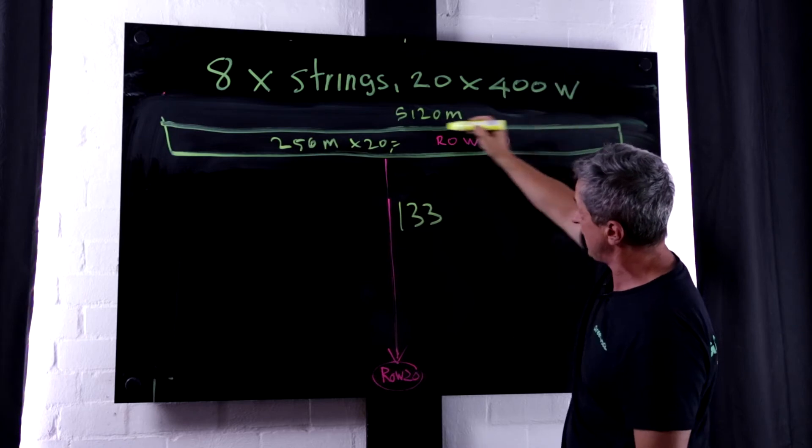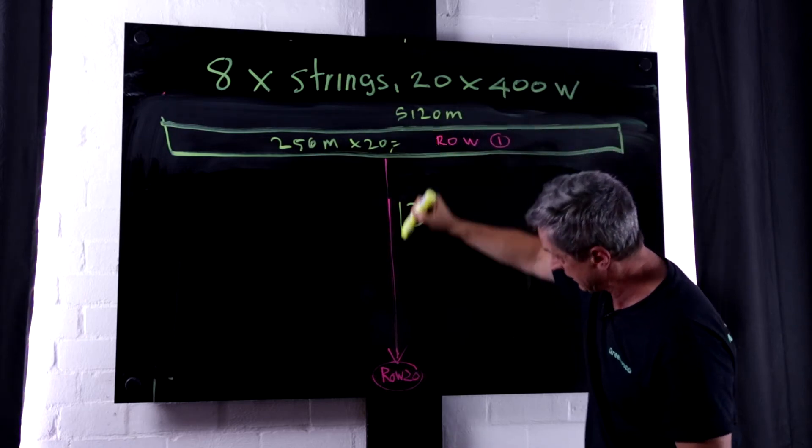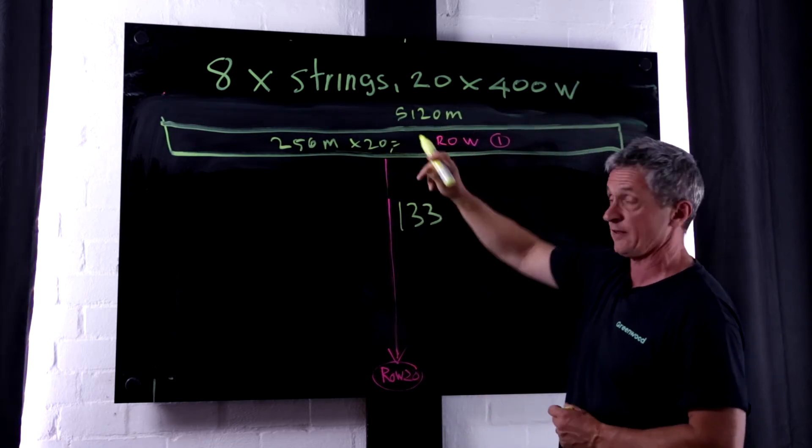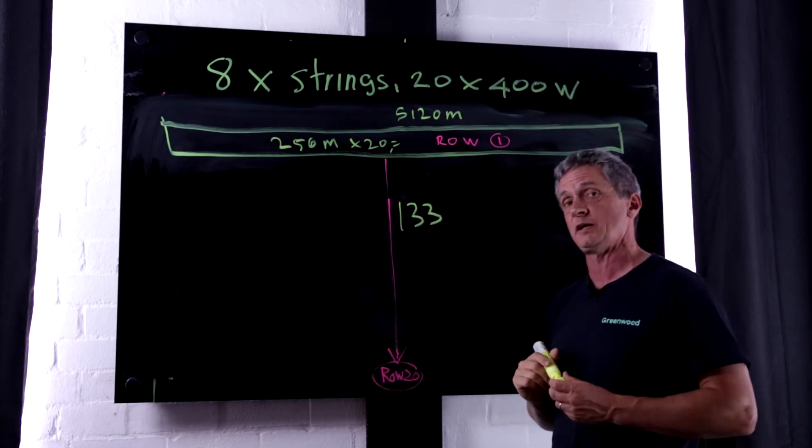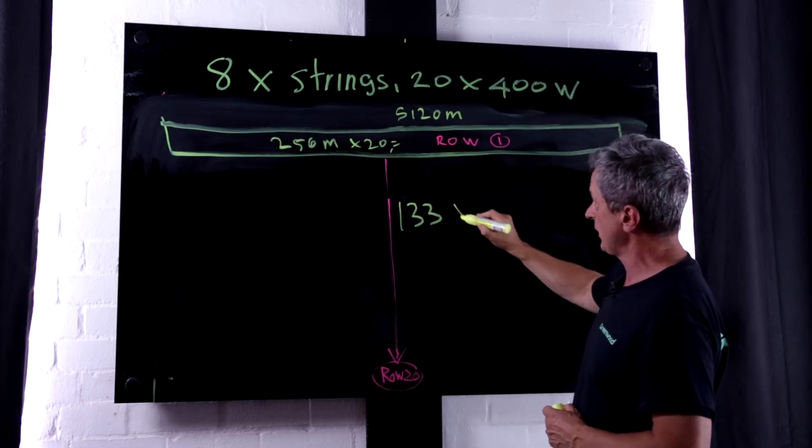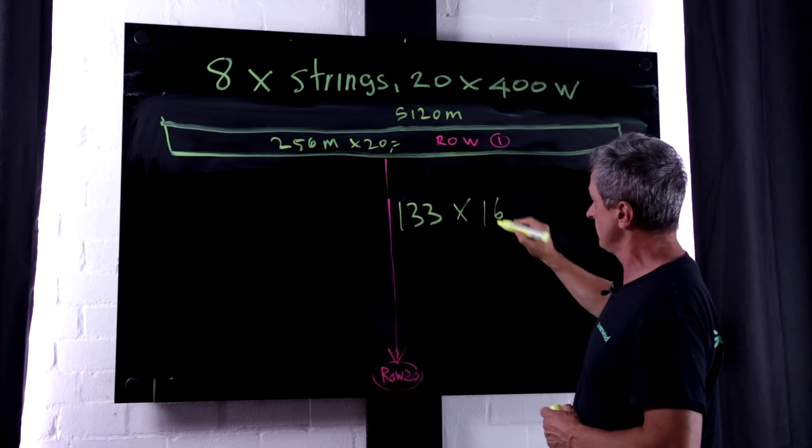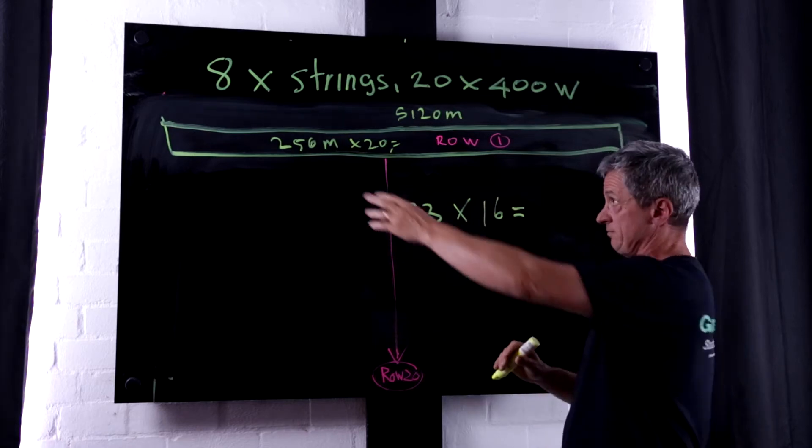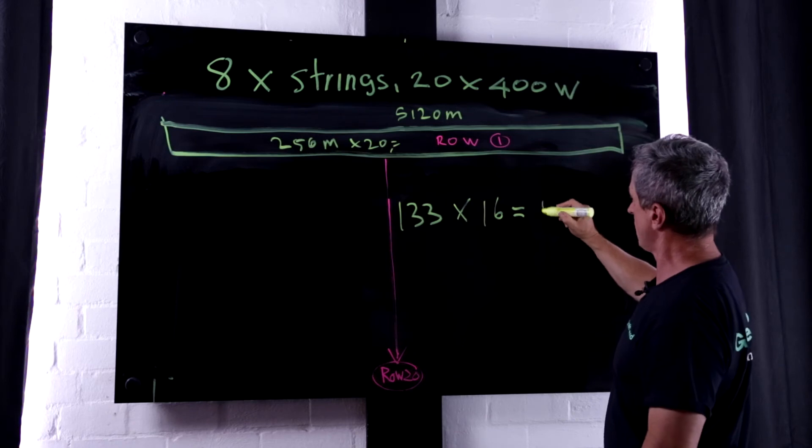But now, we are bringing all the cables to the centre of each row, and there's a run down to the inverter station. Now the furthest run is 133 metres. So we have 133 metres times 16 cables, because there's eight strings, for row one.